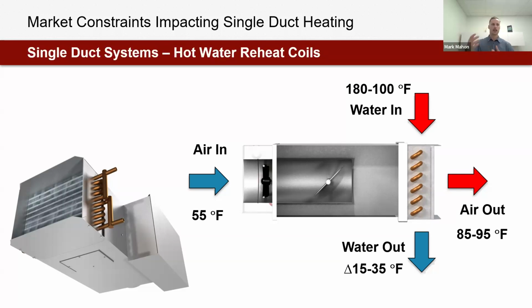And when we look at the water temp in 180 to 100 water temp out, we're generally trying to get some kind of delta T of 15 to 35, maybe 40, depending on the coil system we're using. One thing that I really like to note for single ducts is, of course, they don't really have a coefficient of performance. When we think of this heat exchanger, it's a heat exchanger. All we're doing is exchanging energy from water to air. And if we do that more or less efficiently, we're not losing that energy. It's just going back to the boiler or back throughout the system. So that's a consideration which is going to influence and impact some of the discussion we have in this presentation. So something that I wanted to flag.